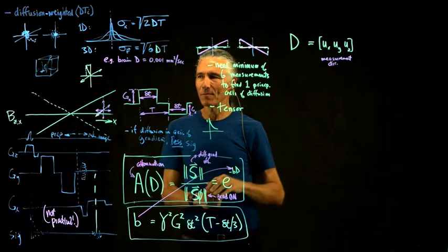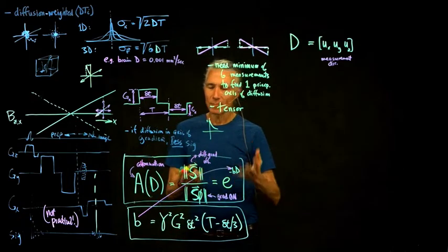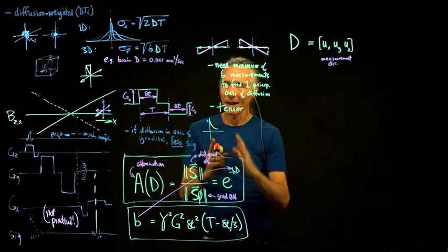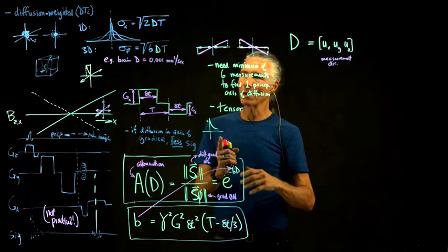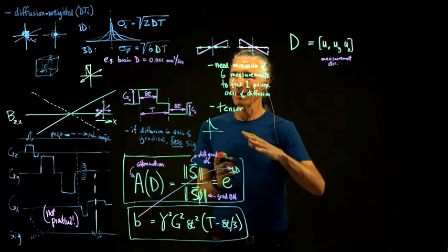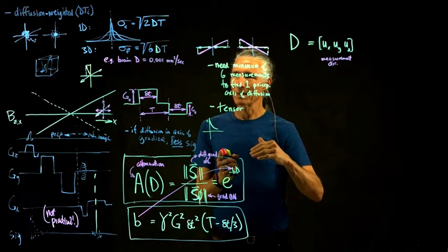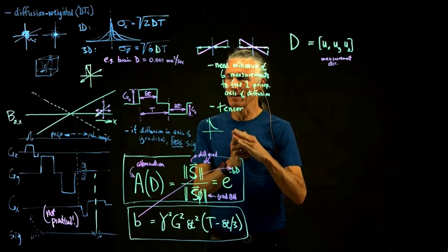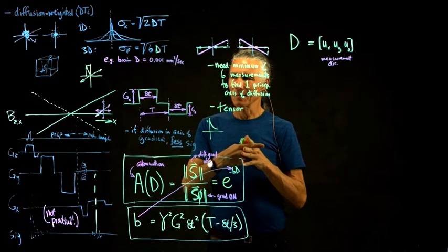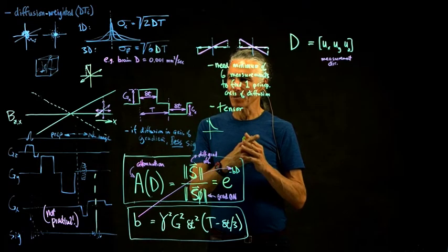We talked about that before. If you want to put on diagonal stripes, you just turn on the X and the Y gradient at the same time, and that will effectively give you diagonal spin stripes because it effectively rotates the gradient direction. It doesn't just sort of add to it, it actually rotates it.